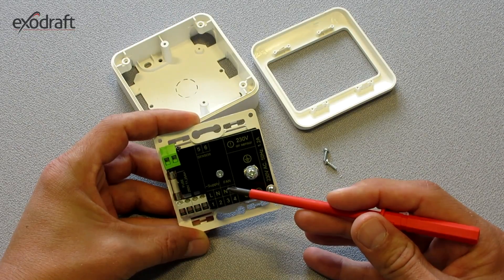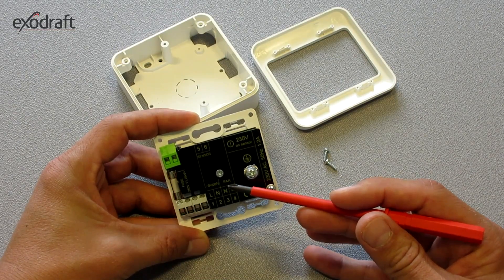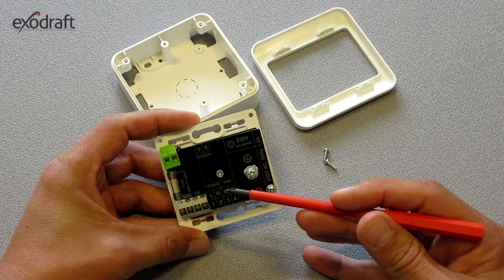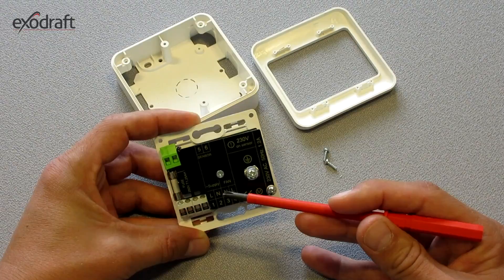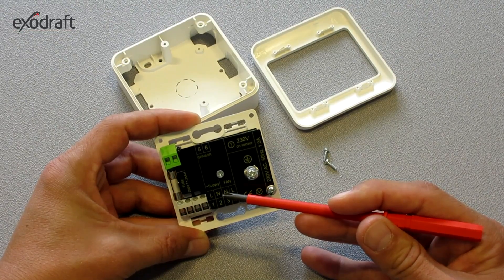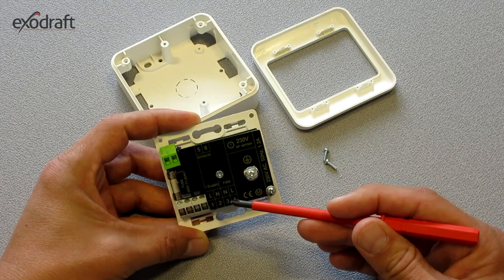In other cases, it may be necessary to ensure that there is voltage between 80 volts and 190 volts from the control unit to the fan. This can be tested by using a voltmeter and is measured between the terminals 3 and 4.